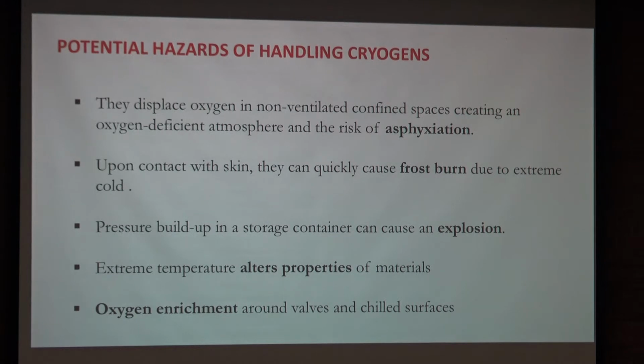One thing to keep in mind is that in a storage vessel there can be inadvertently or advertently a buildup of pressure, since the gas is always stored near its boiling point. And when this is not properly taken care of, this can create an actual explosion hazard.